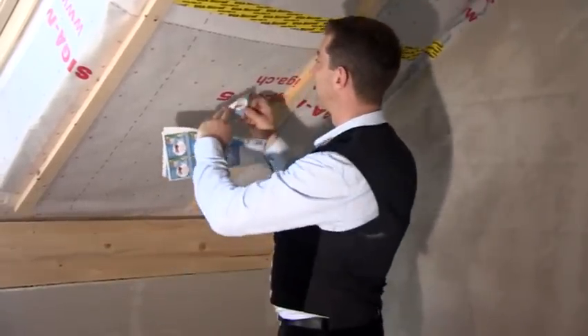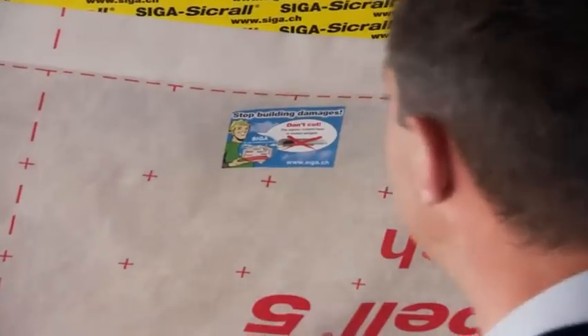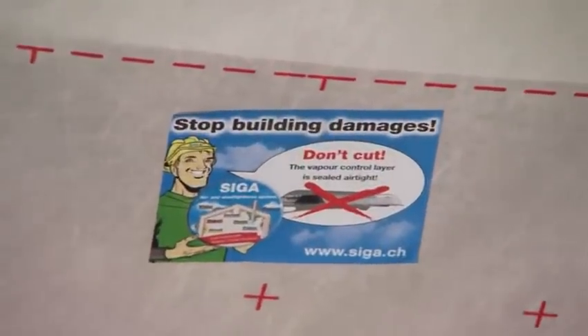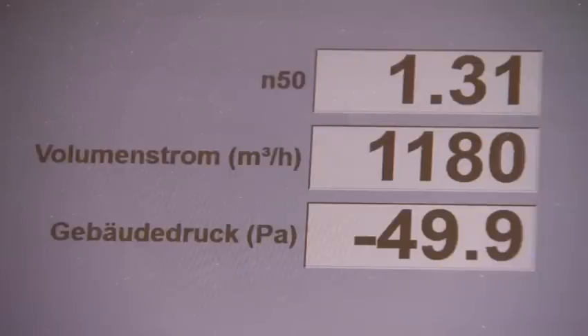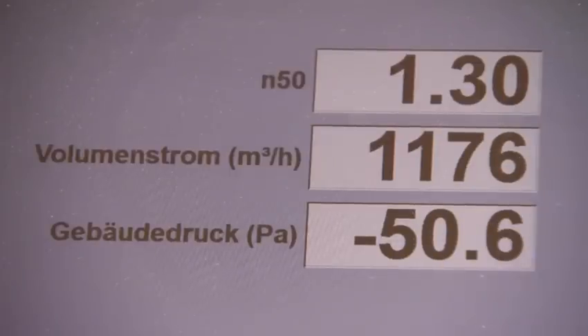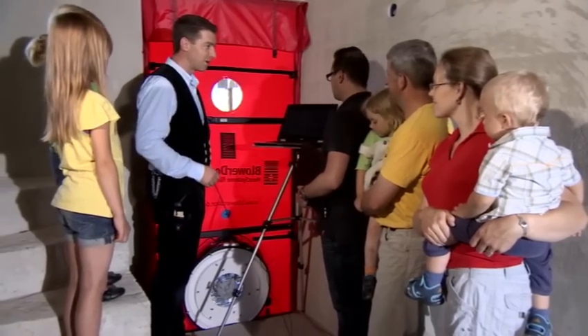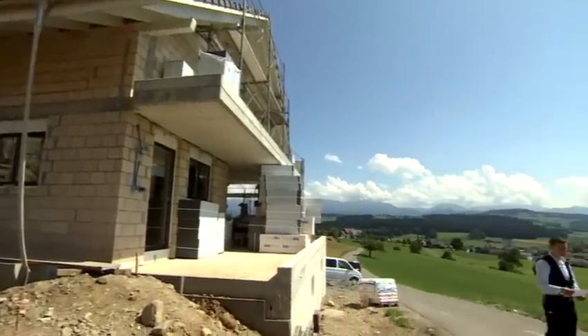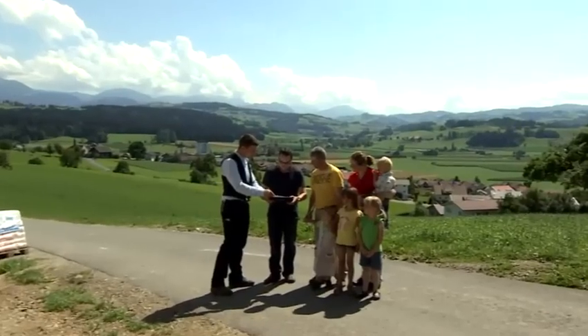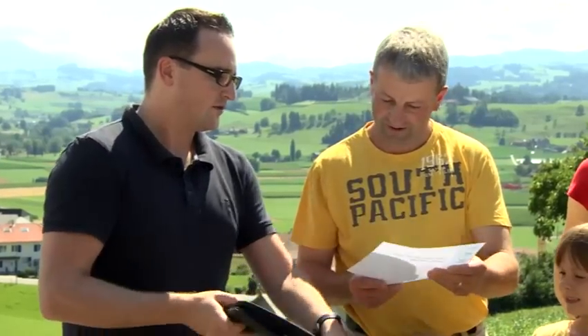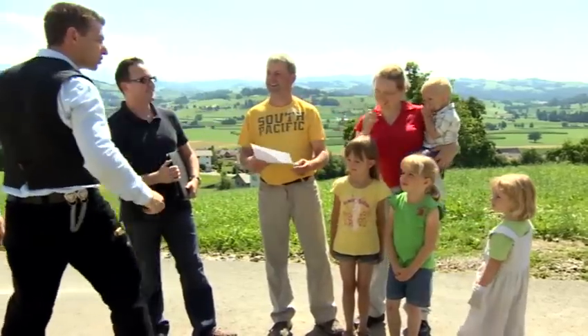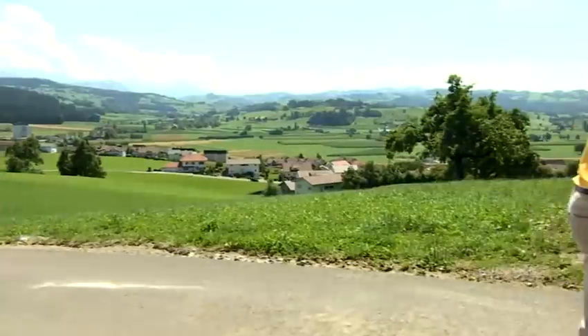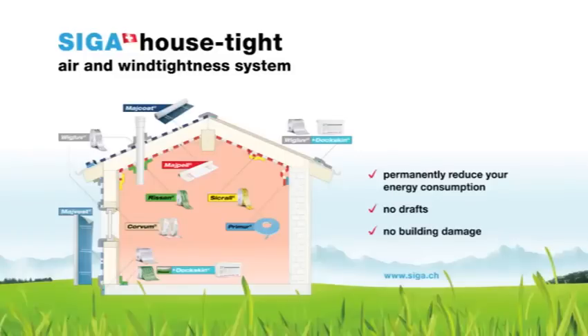The professional secures his work by applying a warning sticker. Finally, the craftsman repeats the blower door measurement in the presence of the building owner and the architect. What improvement has been achieved by the corrections? The air change rate is now well below the required maximum of 1.5. The architect hands the building owner a test record for the measurement that was performed. The SIGA house-tight air and wind tightness system reduces heating costs, eliminates drafts, and prevents building damage.